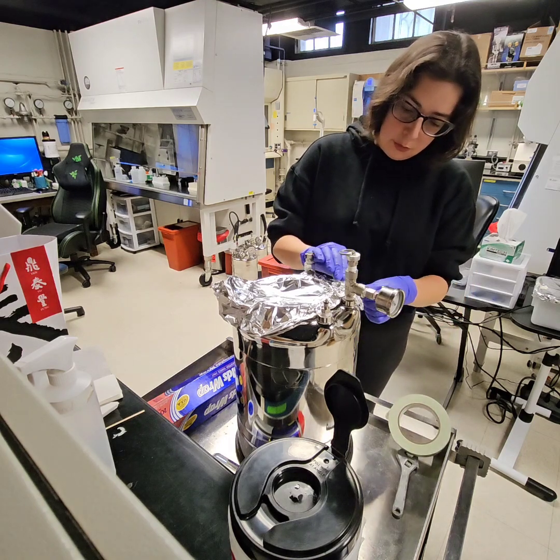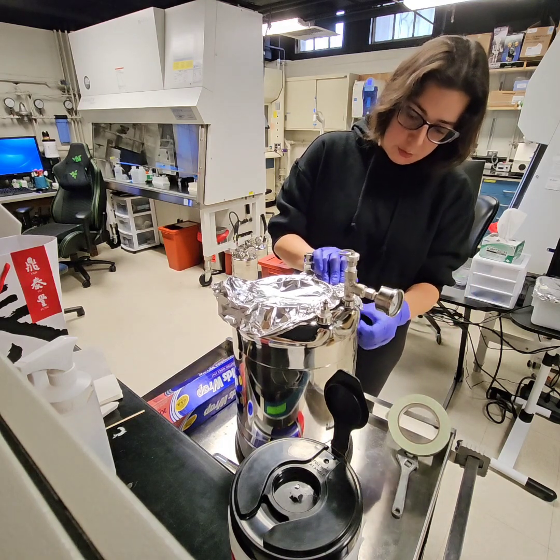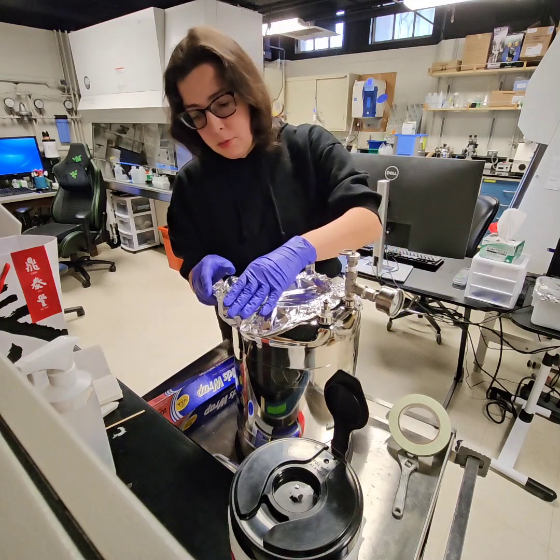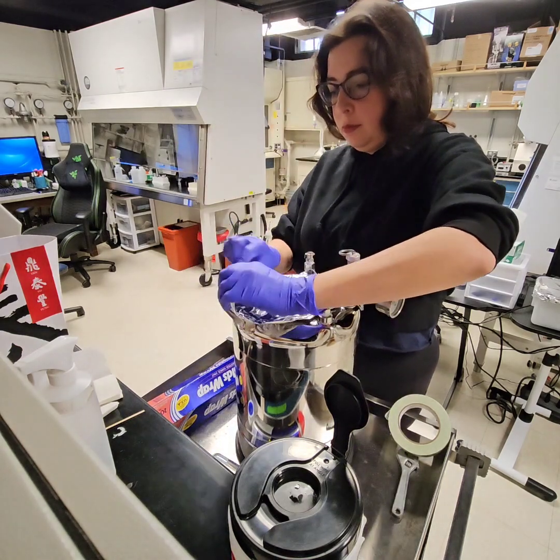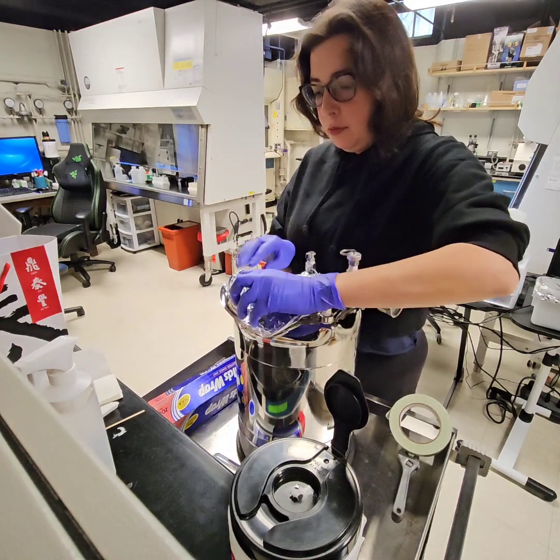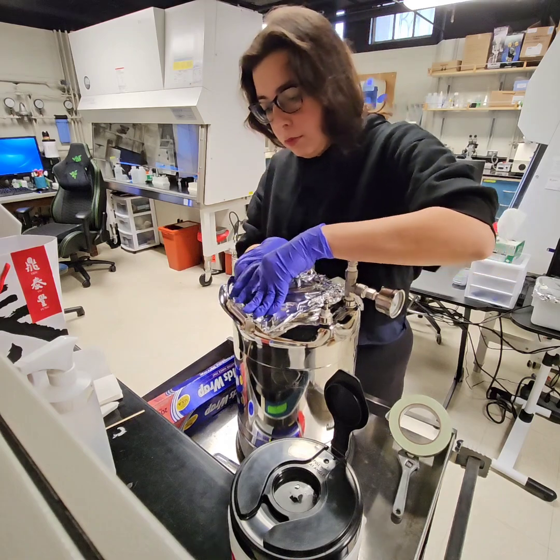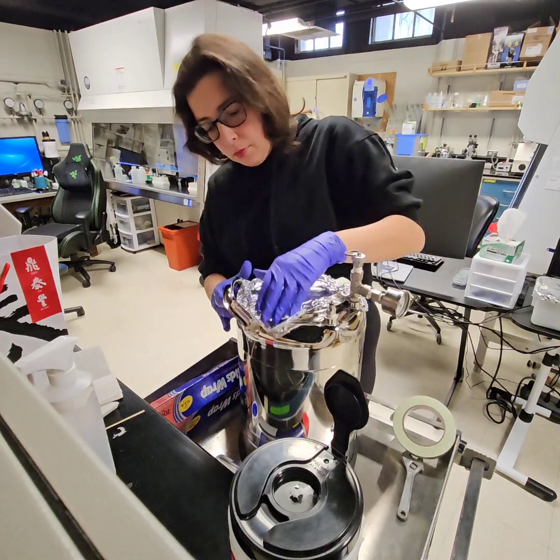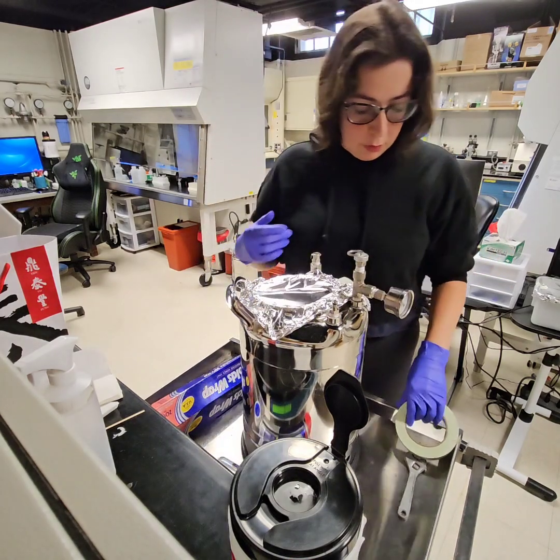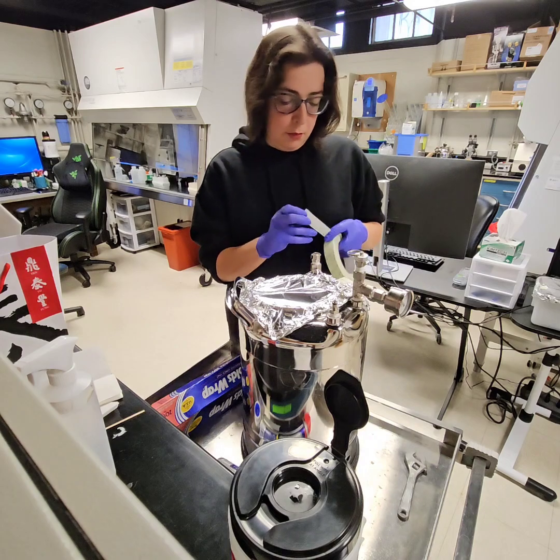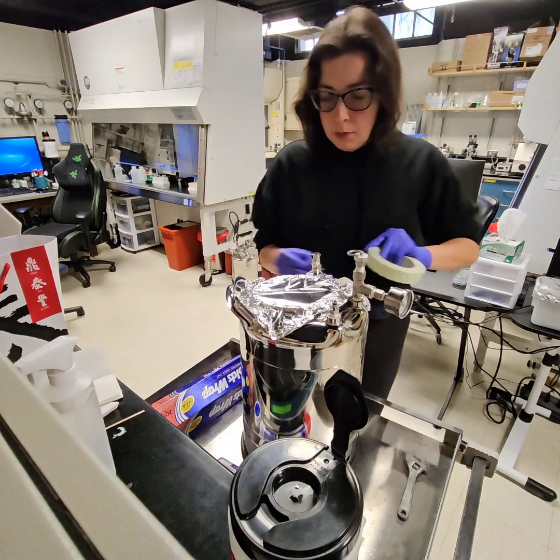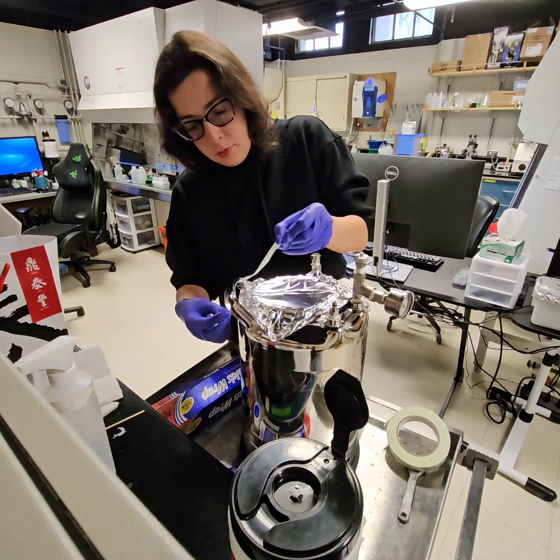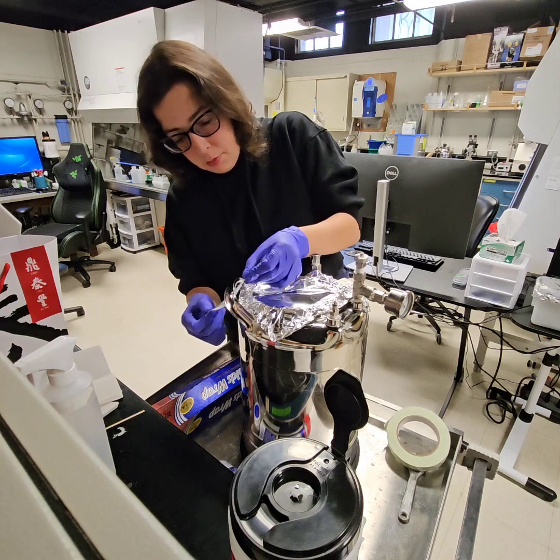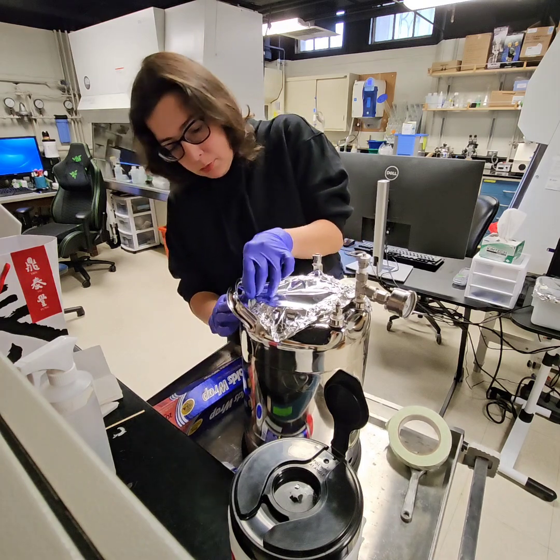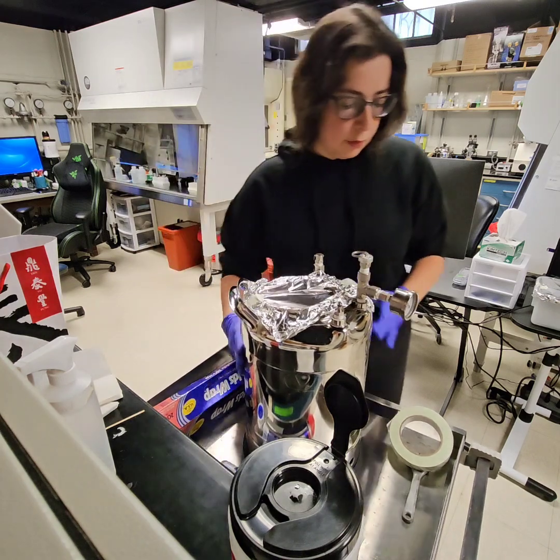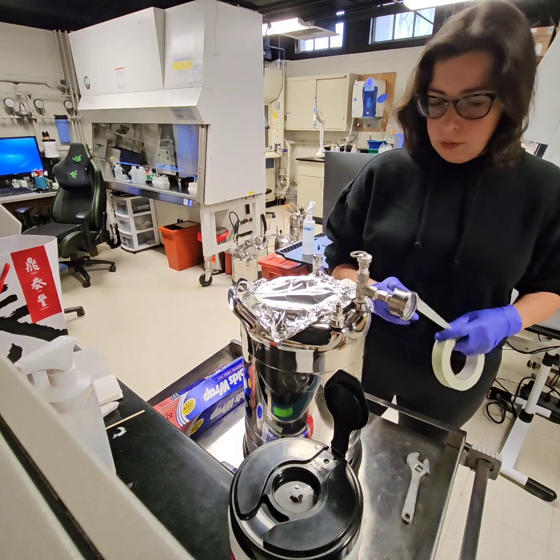So that's why before we cleaned off the remnants of the autoclave tape, because from previous autoclave runs, some of that goo gets left behind. And if you never maintain it, then it's just going to be covered in goo, because it's not like you autoclave this once and never autoclave it again. You want to do this on a regular basis or before any submicron sort where you're going to be running without a filter. Then the next pieces that we're going to cover are going to be all of the connections.